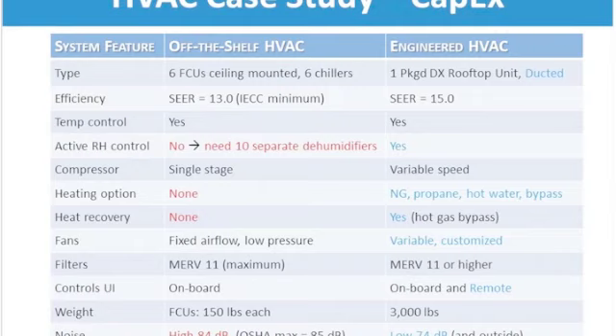For active relative humidity control, with the off-the-shelf system, a lot of times you need to provide a separate source or method of dehumidification, maybe standalone units, or a different type of system that can do the dehumidification your air conditioner cannot do, especially when the lights are off and there's no heat in the space. The engineered HVAC system, we're going to choose something that has dehumidification control no matter whether the lights are on or off. For the compressor, it's a single stage for the off-the-shelf system, and the engineered system is variable speed, meaning it adjusts its operation based on the conditions in the room, as well as the set point targets you've set.